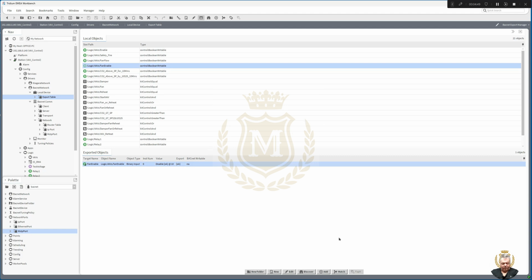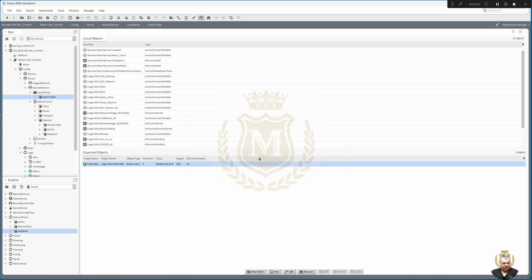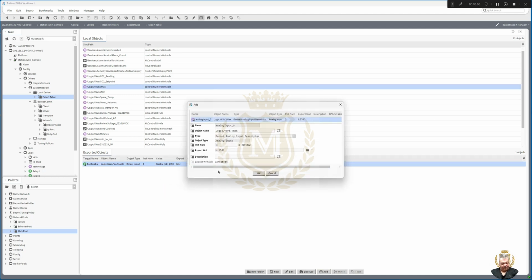Now we'll do one where we can write to. So I'm going to go discover again, and this time I'm going to just select a numeric point, and we said Vmin and Vmax, didn't we? So there's Vmax, drag it into there. Now there's no INs at the bottom here, you can't see any. It's not BACnet writable, cannot edit it. So select your type and go to analog output descriptor.